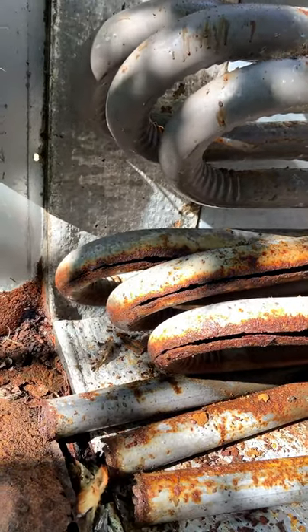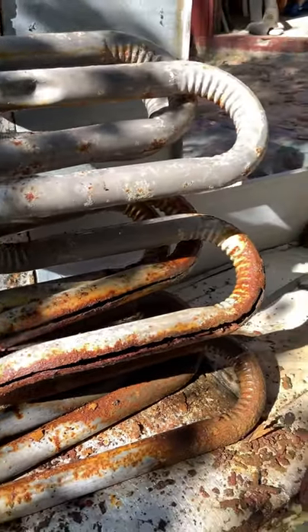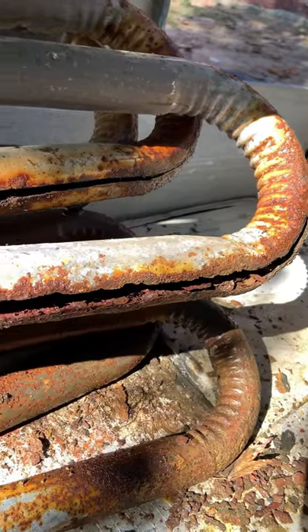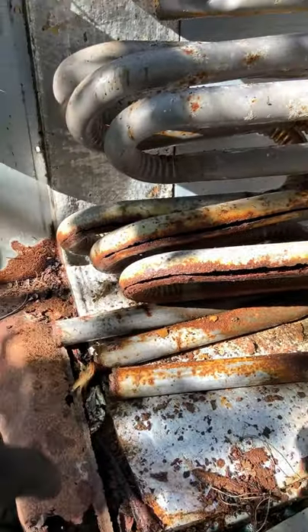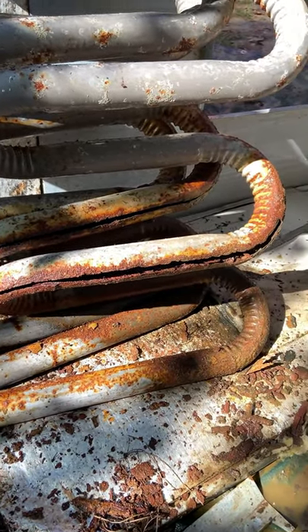This unit was rode hard and put up wet, so to speak — it went through a lot through its lifetime. It's a Nordyne gas pack, and you can just see how susceptible this area is to having cracks. It can be hard to see because it's closer to the bottom, so you can't see it when you take off the top.